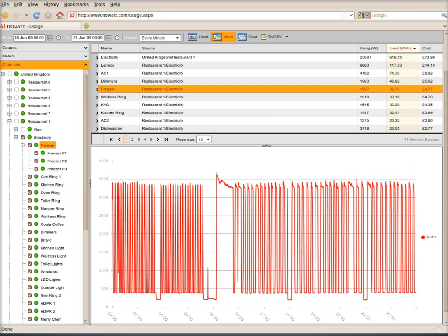But more excitingly, you can actually see in that top right hand grid the consumption's dropped down to around 40 kilowatt hours per day. I mean, that's 73 kilowatt hours per day less. That's 73 kilowatt hours that would have gone unnoticed, maybe for months, maybe for years. That's £2,500 a year they'd have been wasting if they were relying on half-hourly data and their intuition.